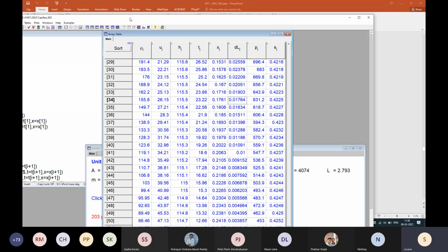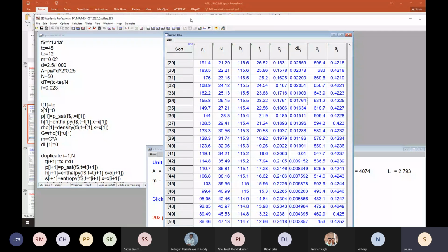So you don't have to write a code in any exam or tutorial. I'm just telling you how we actually size. Now ASHRAE has done a very important thing, they have tabulated the length and diameters for various refrigerants for various operating conditions. So in the field, if you have to size, you just have to look into that table or a chart. But how that table or chart is created is through this process.